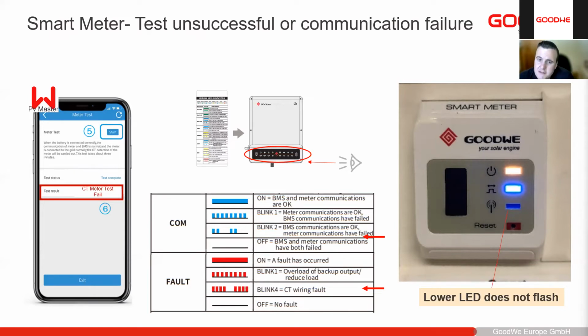Next is the smart meter test. First, when we're on site busy commissioning, we're doing the smart meter test. We've checked the smart meter, made sure that the power LED is on and the LED for communication is flashing, so it is communicating. Very often, our inverters are slightly further from the smart meter than the cable that is provided. Normally, in those instances, you can extend that cable. If you extend it, please don't use extender leads, one of those clip-in extender leads. Because it's RS485, the more parts you introduce, the more chances you have for interruptions.